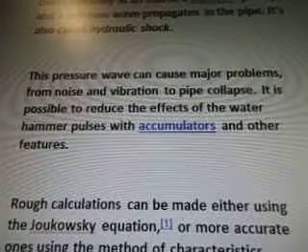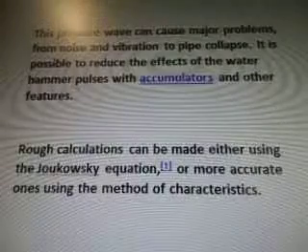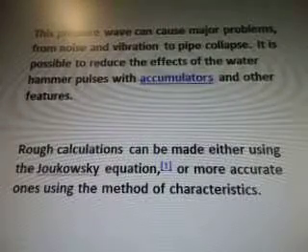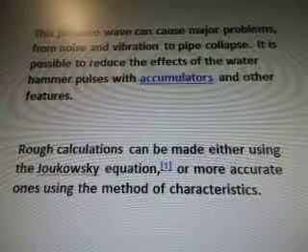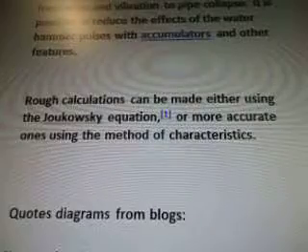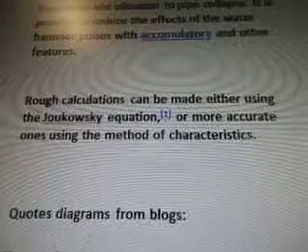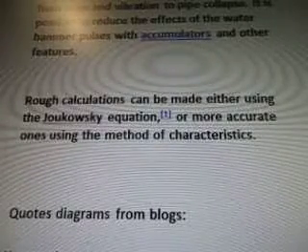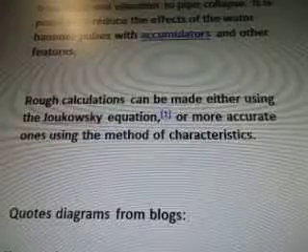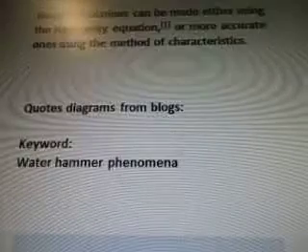It's also called hydraulic shock. This pressure wave can cause major problems, from noise and vibration to pipe collapse. It is possible to reduce the effects of the water hammer pulses with accumulators and other features. Rough calculations can be made either using the Joukowsky equation, or more accurate ones using the method of characteristics.